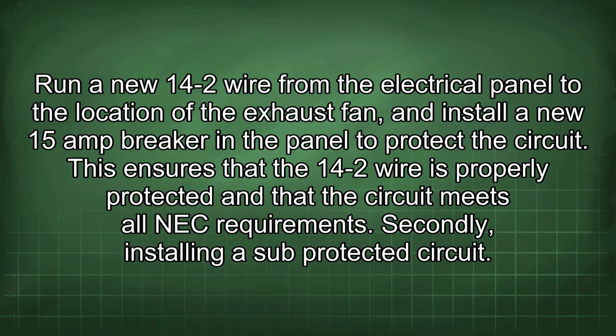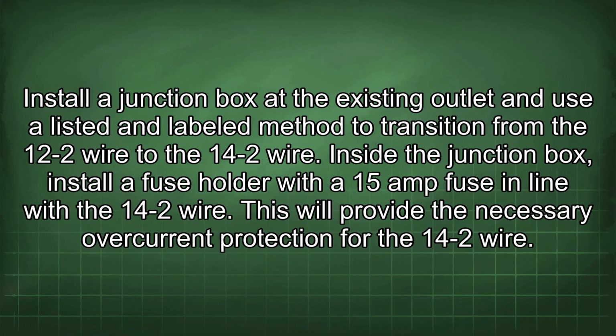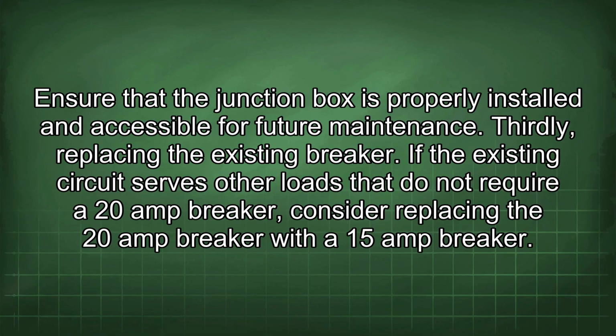Secondly, installing a sub-protected circuit. Install a junction box at the existing outlet and use a listed and labeled method to transition from the 12-2 wire to the 14-2 wire. Inside the junction box, install a fuse holder with a 15-amp fuse in line with the 14-2 wire. This will provide the necessary overcurrent protection for the 14-2 wire. Ensure that the junction box is properly installed and accessible for future maintenance.